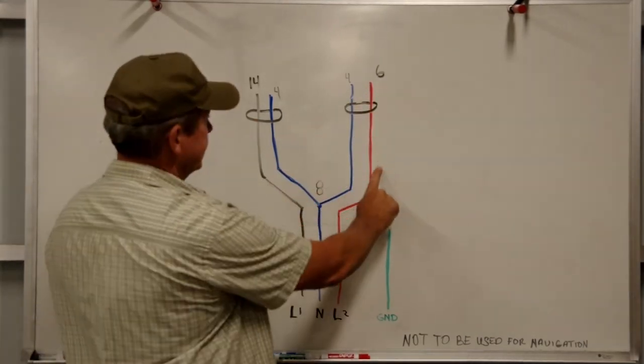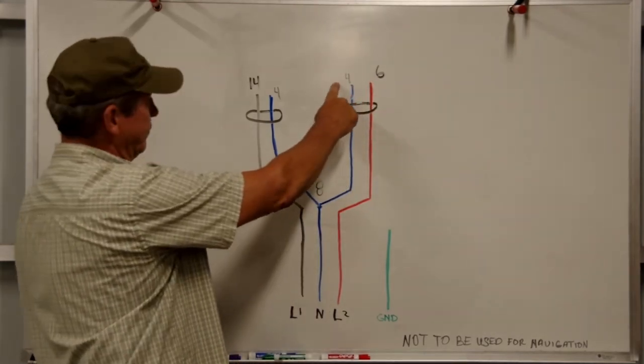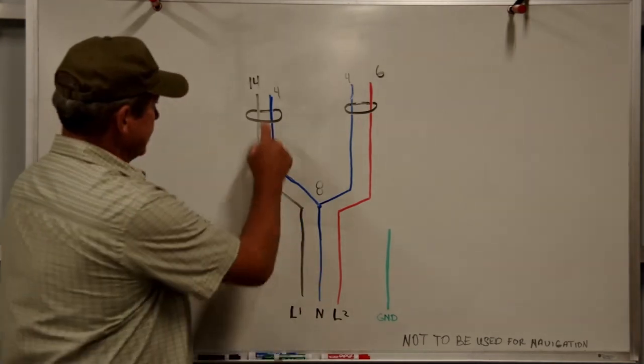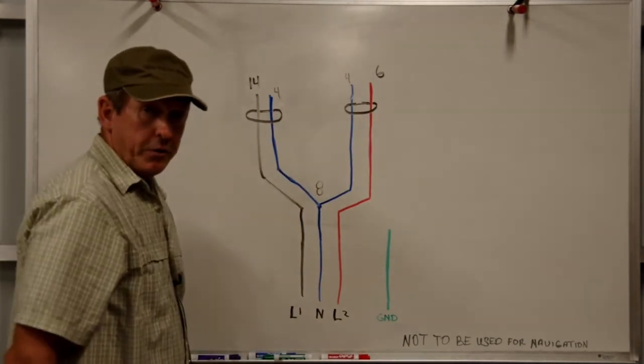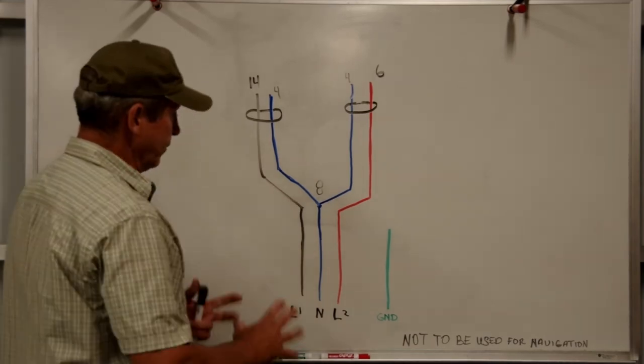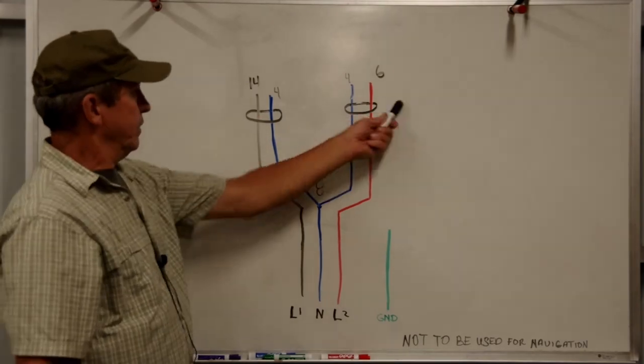Line two, we'll have six coming in, but we only, again, we have four on our neutral and, again, an imbalance. So, these two ground fault breakers will trip. Even though our boat has no fault current on it, we're just creating an imbalance with the splitter.